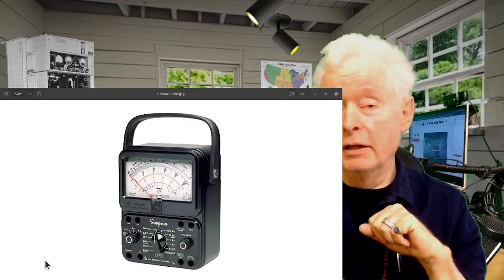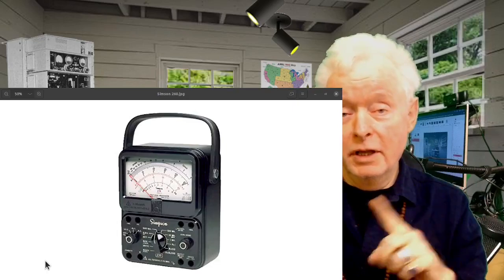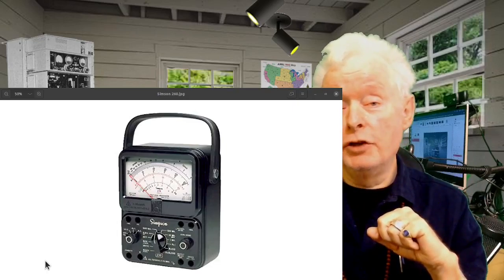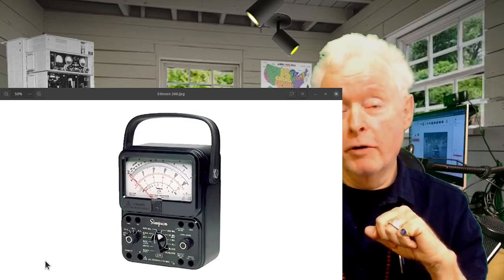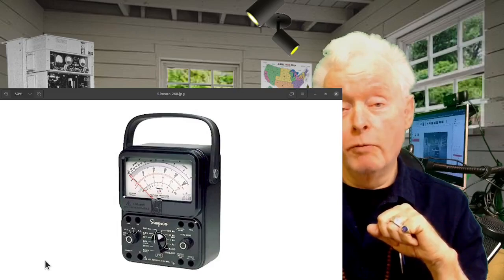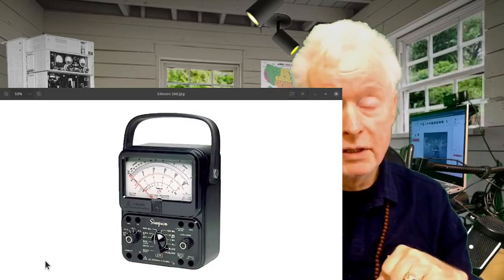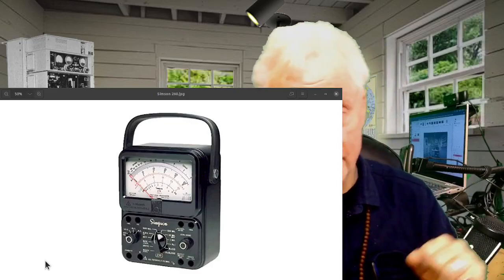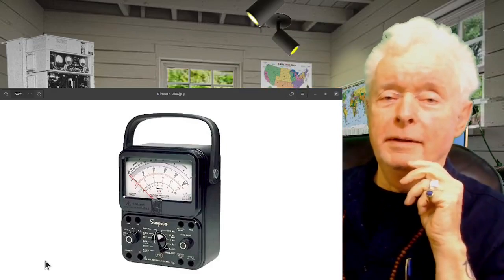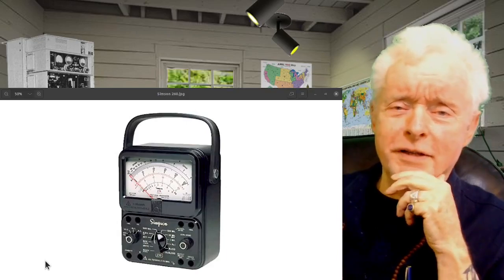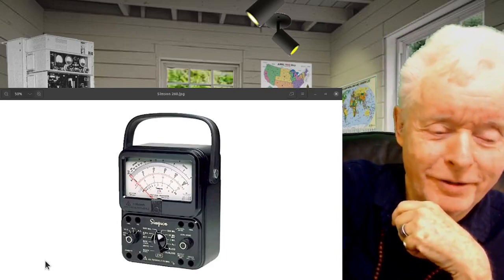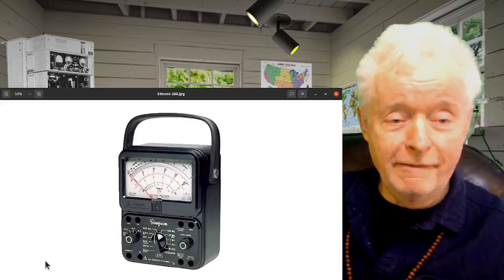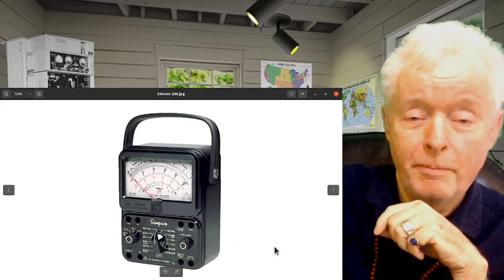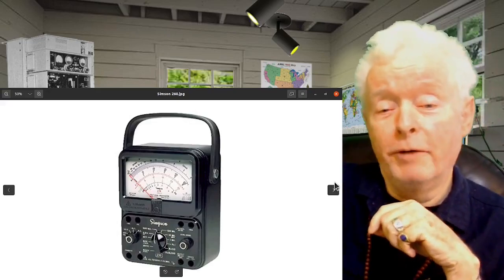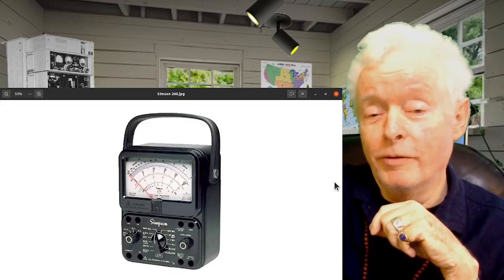So if you're reading on a 100-volt scale, you could be assured that anything that you read using the mirror correctly would yield you a measurement that was within 1 volt. 1% of full scale. I have to adjust myself to the screen here. So, moving on. And by the way, this is not going to be in any particular order.